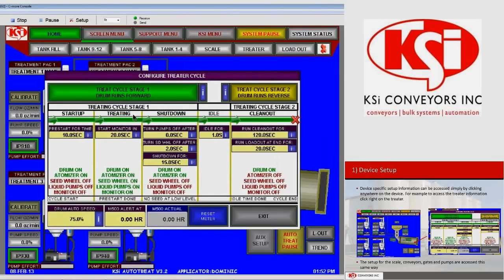The next column is the treating stage during stage 1, and all we're doing here is we can see that all the equipment is turned on, and we just have a start monitor in 20 seconds. Once the seed wheel or the gate have opened up and are delivering seed to your treater and your pumps are on, we want to give the system enough time to get the pumps up to speed before we trigger a fault. That may be 20 seconds. You may tighten that window down to 10 seconds, whatever that might be. After this 20 seconds, our fault monitor for our pumps is going to turn on, and they're going to fall out after this time if the pumps fall out of tolerance.